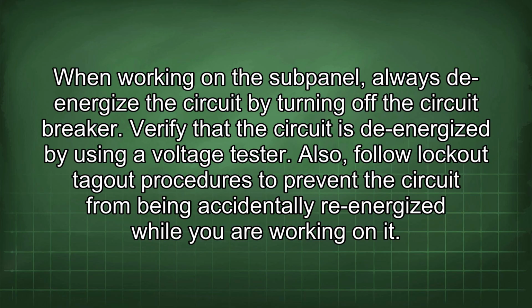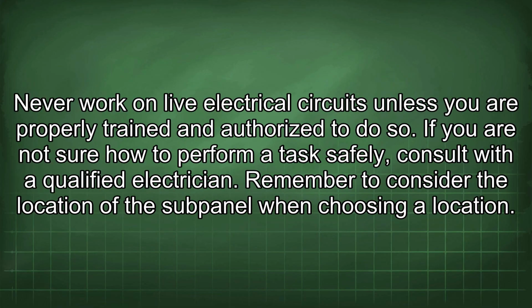When working on the subpanel, always de-energize the circuit by turning off the circuit breaker. Verify that the circuit is de-energized by using a voltage tester. Also, follow lockout-tagout procedures to prevent the circuit from being accidentally re-energized while you are working on it. Never work on live electrical circuits unless you are properly trained and authorized to do so. If you are not sure how to perform a task safely, consult with a qualified electrician.